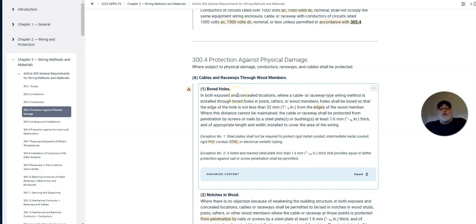So this is going to talk about boring holes in both exposed and concealed locations, where a cable or raceway type wiring method is installed through bored holes in joists, rafters, or wood members. Holes shall be bored so that the edge of the hole is not less than 32 millimeters, or an inch and a quarter, from the edges of the wood member. Where the distance cannot be maintained, the cable or raceway shall be protected from penetration by screws or nails by a steel plate or bushing at least 1/16 inch thick and of appropriate length and width installed to cover the area of the wiring. What does that mean?